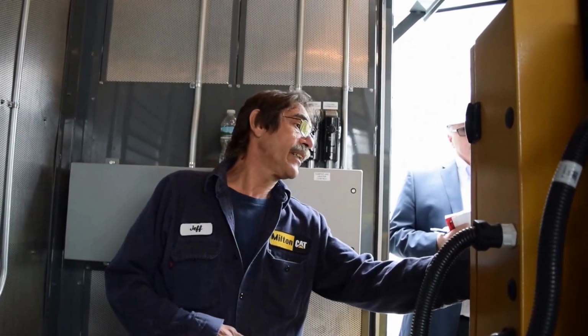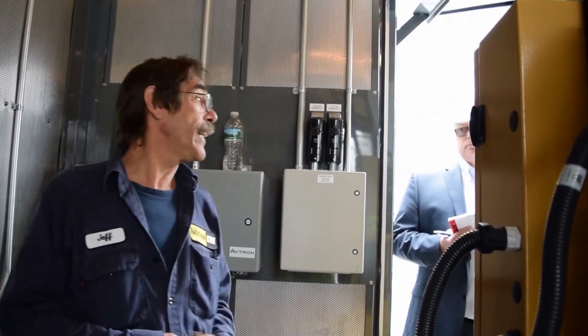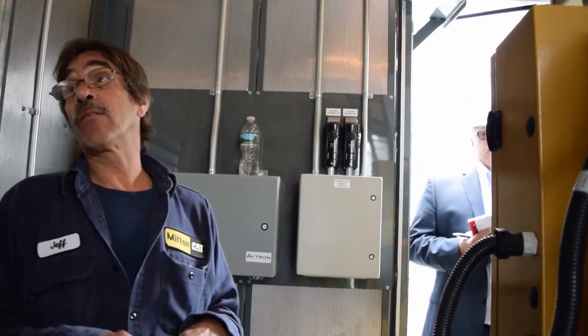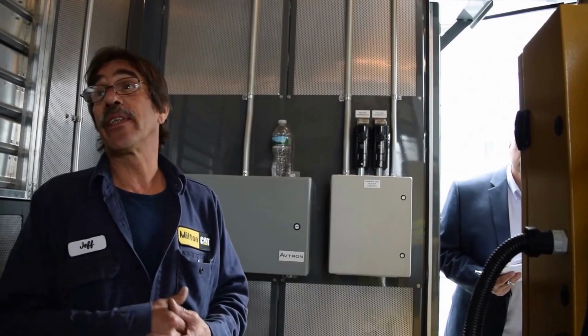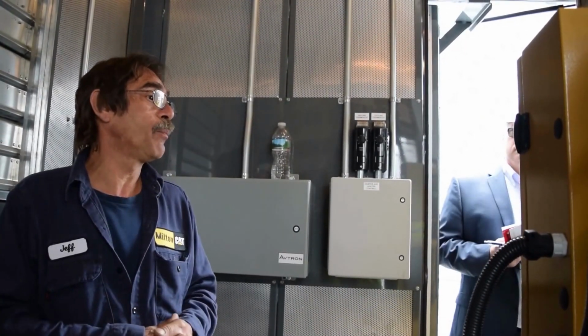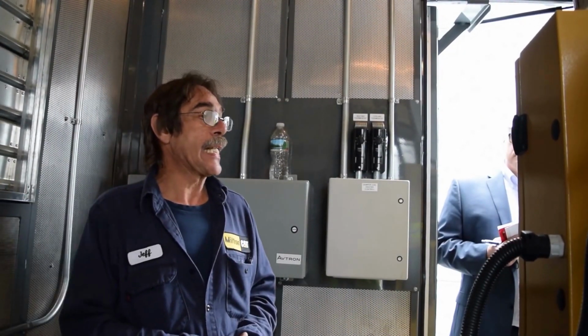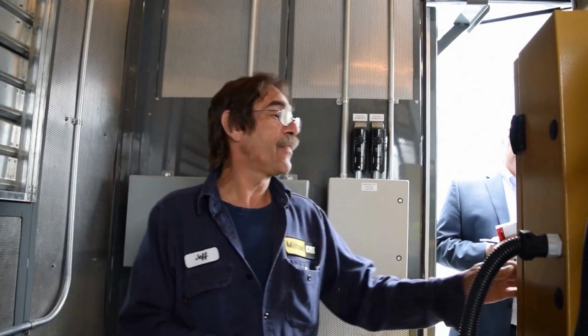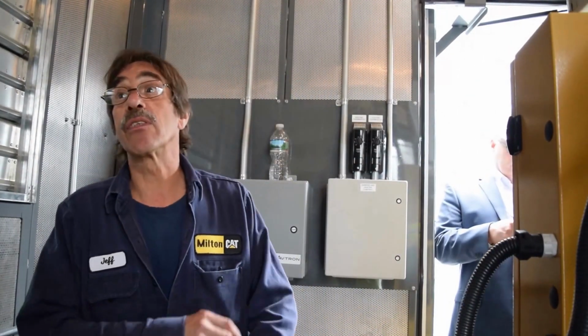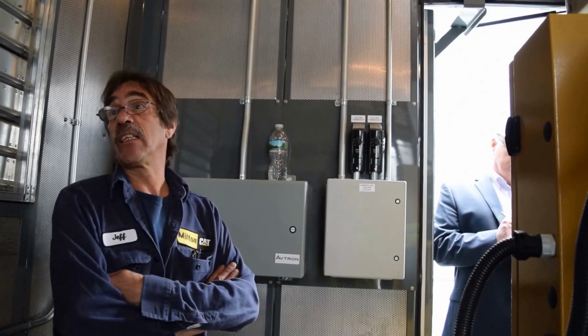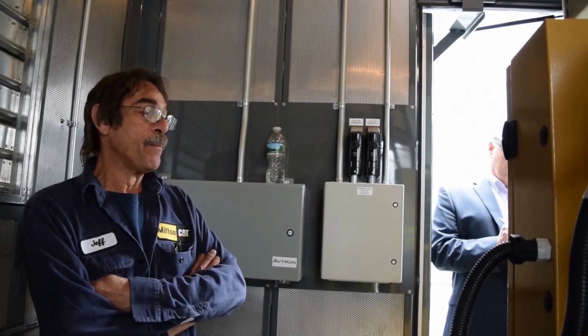Some of them will have a secondary plug on the inside for the second data link. The primary data link runs the show and we don't run accessories off of it. But on this unit, I don't believe there's anything running on that second data link because we have 485 annunciators. Both of them are 485, so there's nothing on that secondary Caterpillar data link.